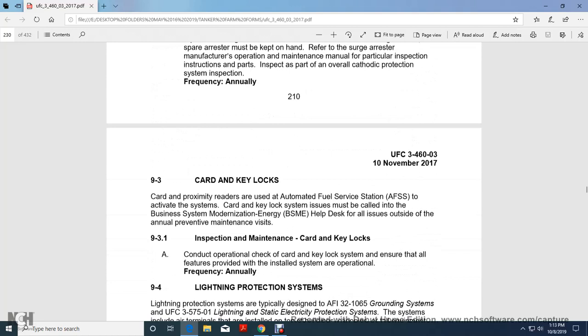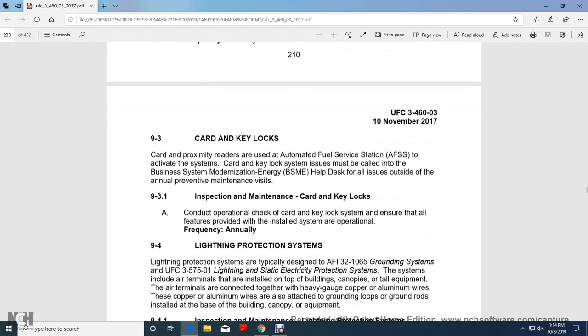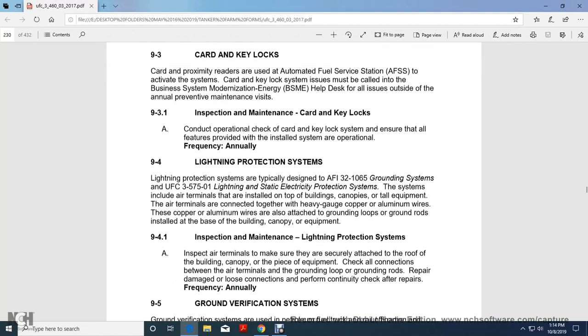Card and key locks, 9.3. Card and proximity readers are also used at automated fuel service stations to activate systems. Card and key lock system issues must be called into the Business System Modernization Energy help desk, for all issues outside of the annual preventive maintenance visits. 9.3.1, Inspection and maintenance of card key locks: conduct an operational check of the card key lock system. Ensure that all features provided with the installed system are operational, annually.